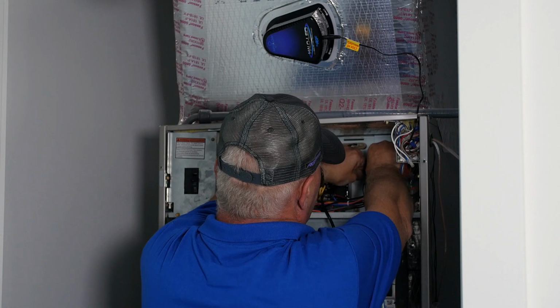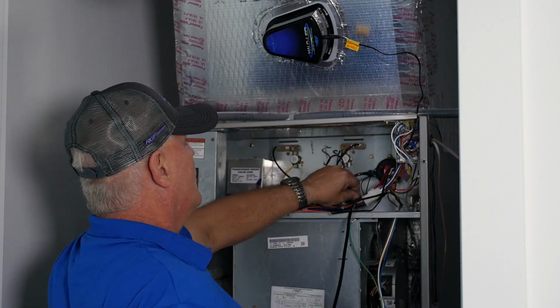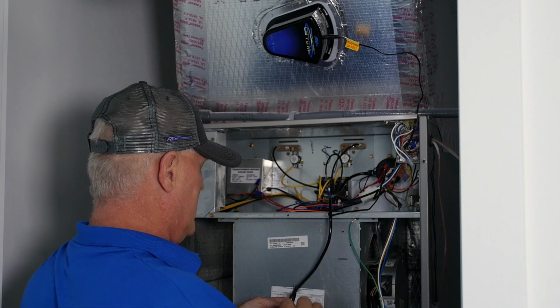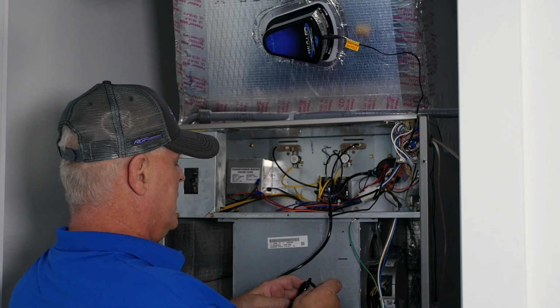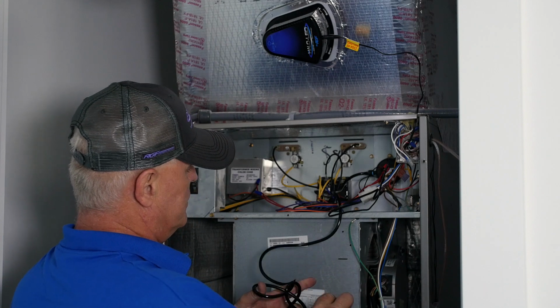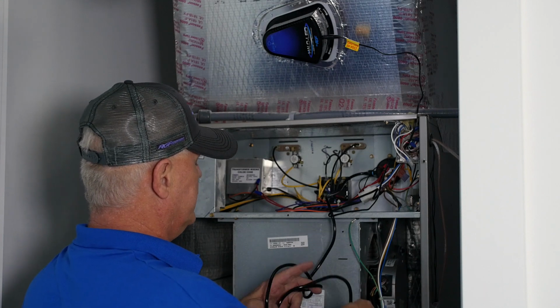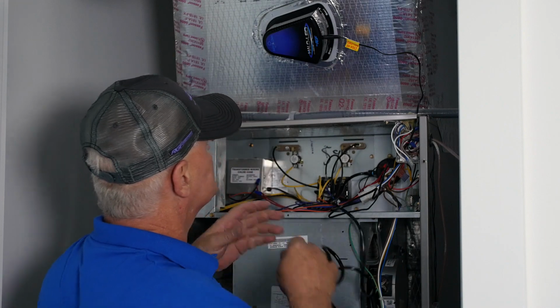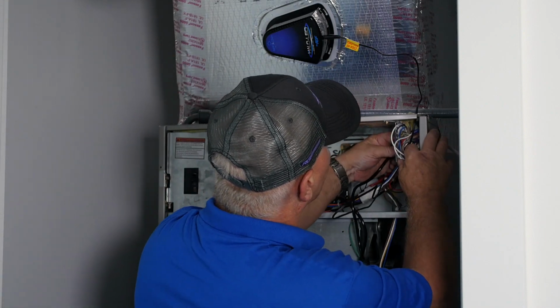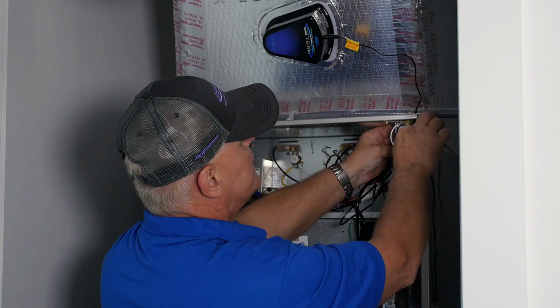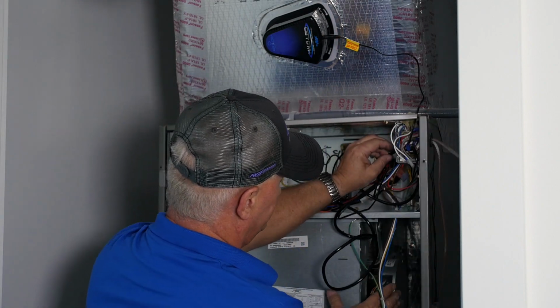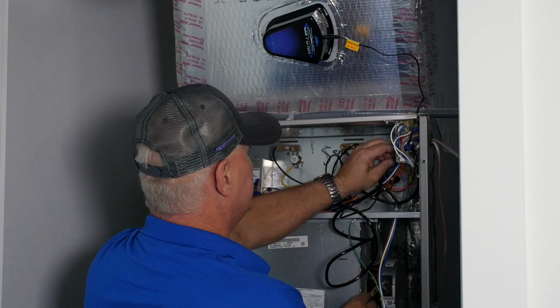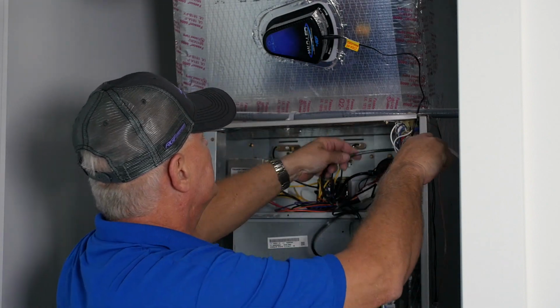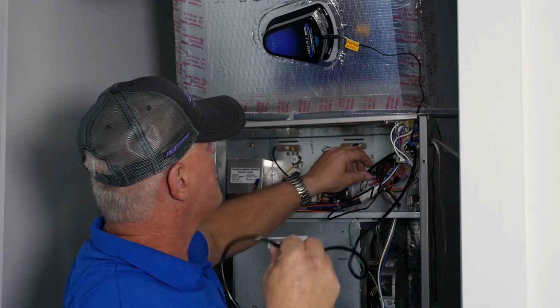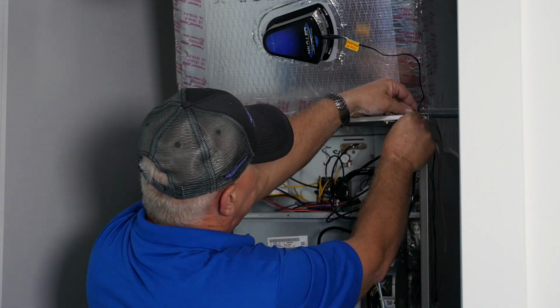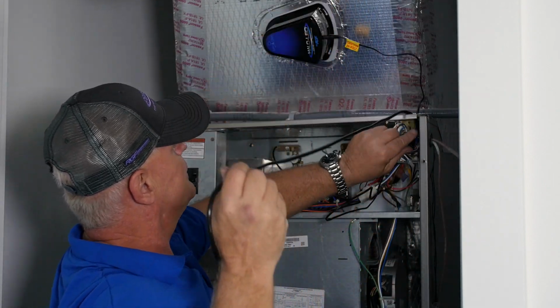And then we're going to follow our wiring out to the REME with the sensor tube. In this instance, you would not necessarily use all of the tubing that we provide in the kit, but in certain instances, you would be running the tubing down to, say, a sealed cabinet. You would actually want to have your intake or negative pressure side here near the blower to get the negative side of the airflow. And then you simply feed up through to the ductwork.